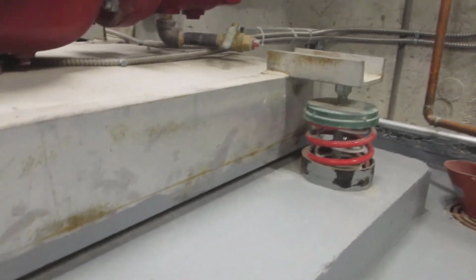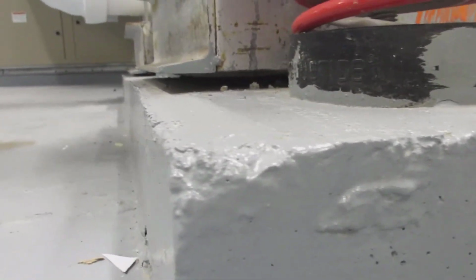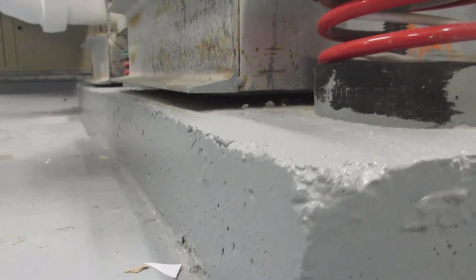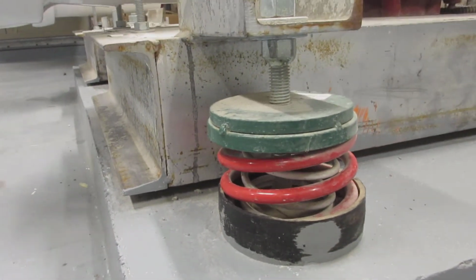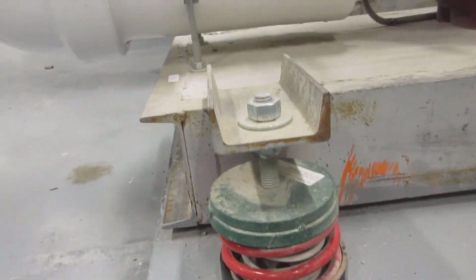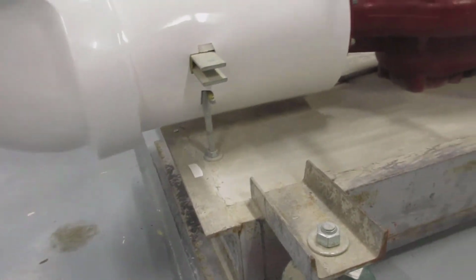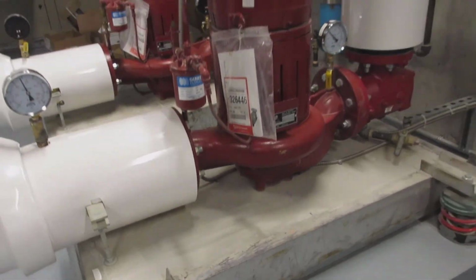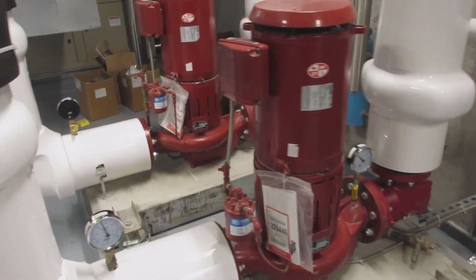Now we'll get down to look under the inertia base and see if the shims have been removed and if there is any other debris that may be short-circuiting the isolation. Notice that the gap is much less than the 2 inches indicated in our submittal, but I don't see anything solid between the base and the floor. This corner isolator seems okay too. Its hold-down nut is secured to the support bracket. Now we'll walk around to look at the other side.